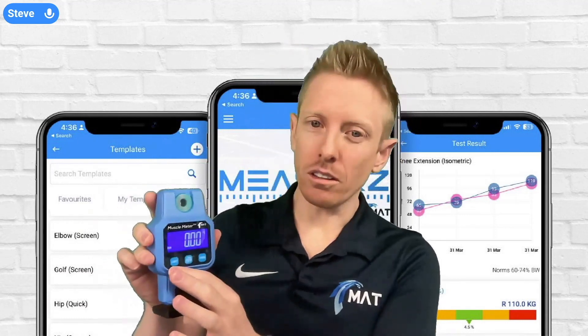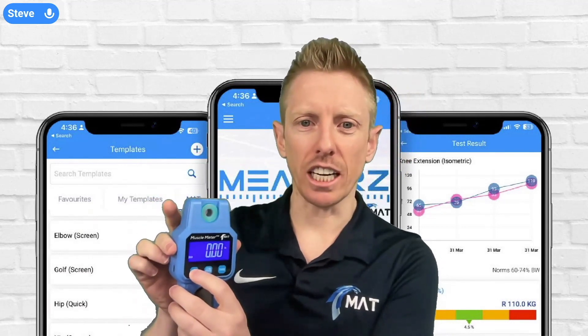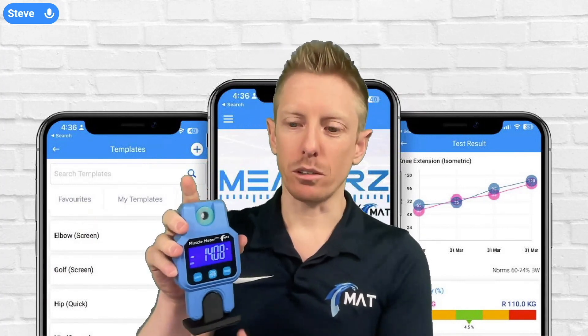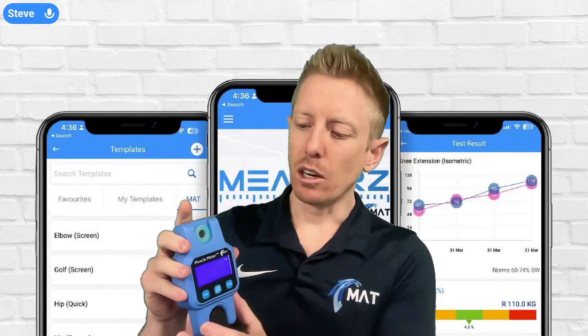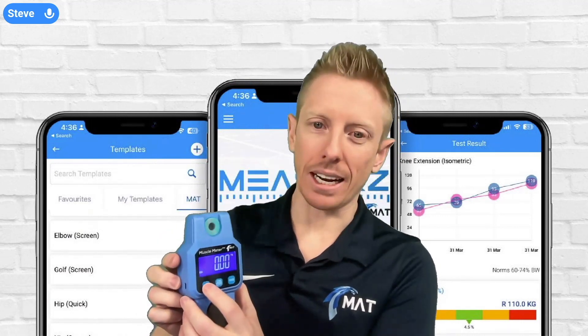The third button is the units button. When you push it you can change from kilograms to pounds — so instead of displaying kilograms, you've got it in imperial pounds for our American friends. If I change it back to kilograms — back to a real unit of measurement — and re-zero, we'll then show the other function of the units button, which is being able to change the mode.